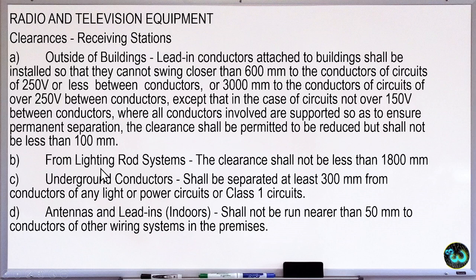For lightning rod system, so this is lightning, hindi po yan lighting but lightning rod system, the clearance shall be not less than 1800 mm. For underground conductors for Class 1 circuit, so the separation must also be 300 mm. For antennas and lead-in indoors, so the run shall not be nearer than 50 mm to the conductors of our normal power or the power conductors.